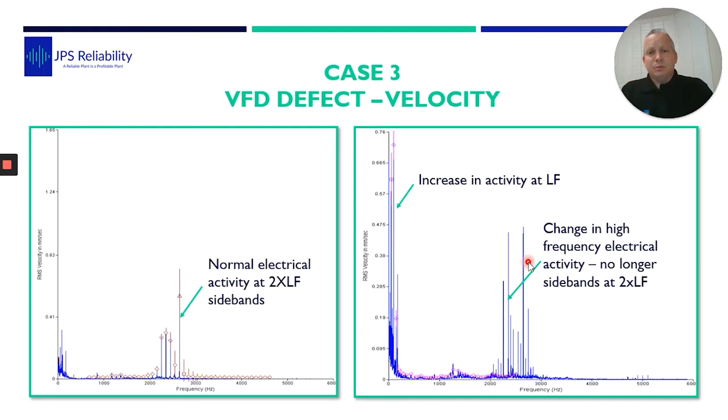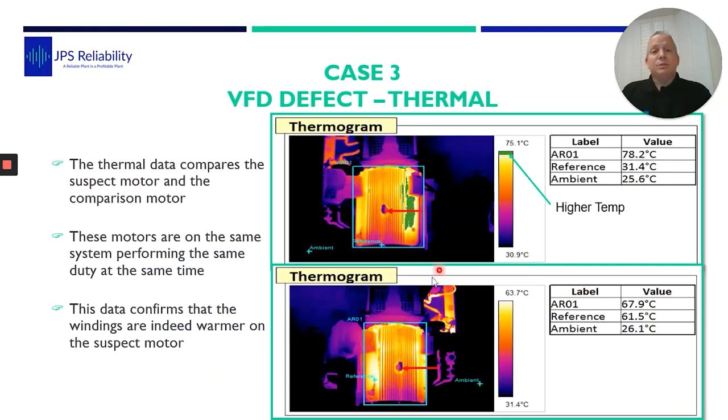So we used thermography, and what was noticed was here on this data, comparing the 2 motors, you can see we're up to 75 and we're 63.